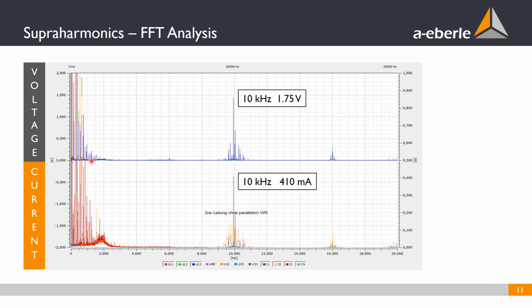Everything you can see here on the left-hand side comes from the classical harmonics, what the EN50160 standard is evaluating. Everything here on the right-hand side, this is the so-called supraharmonic voltages and currents. In this case that we saw before, we can see here that there was a current of about 400 milliamps causing a distortion on the voltage of 1.75 volts. Now, of course, the interesting part is how to evaluate this.